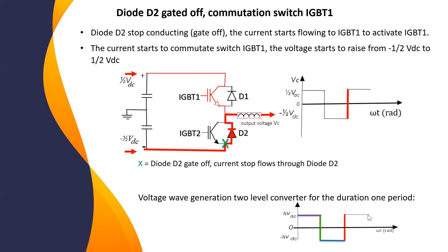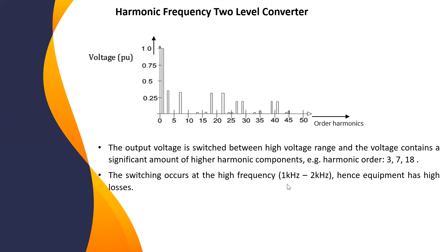Because we switch the converter between positive and negative, the harmonics are very high, since we switch the valve with high voltage. High voltage means harmonics, and we also generate harmonics in this submodule valve. Similarly, for the 2-level converter, we switch our valve with high frequency, 1 kHz to 2 kHz, and at the end we have high losses here.